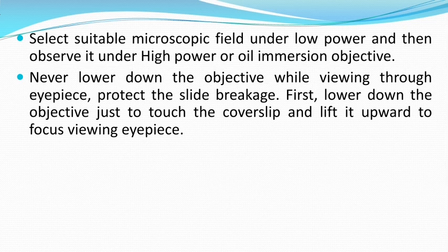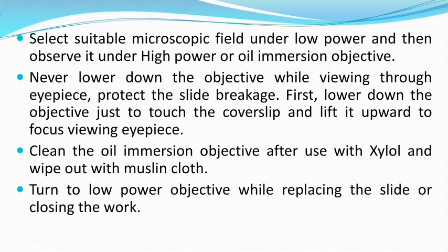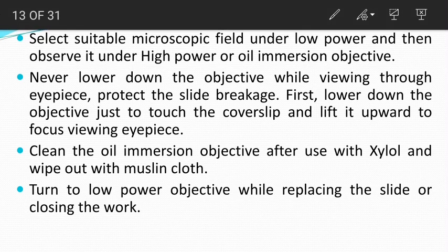Protect the slide from breakage. First lower down the objective just to touch the cover slip and then lift it upward to focus while viewing through the eyepiece. It means take care of slide breakage. Clean the oil immersion objective after use with xylol and wipe it with a muslin cloth. Turn to the low power objective while replacing the slide or closing the work.